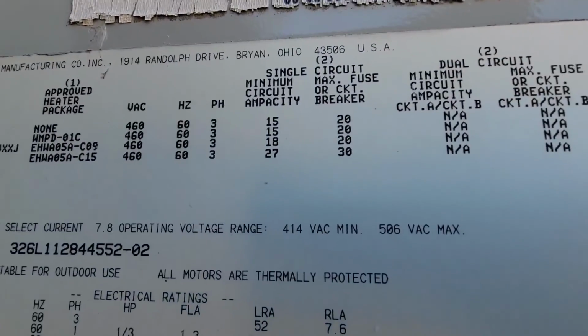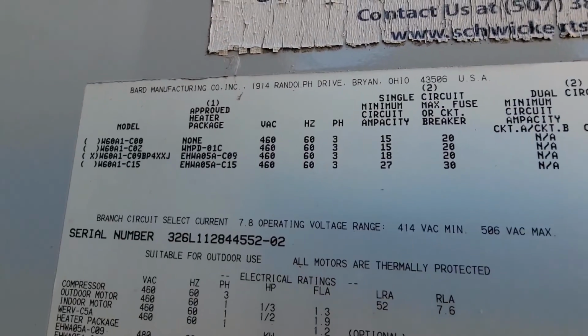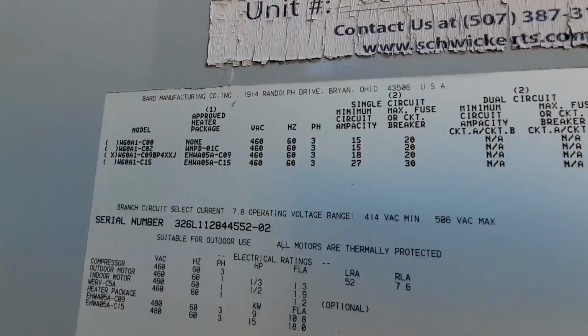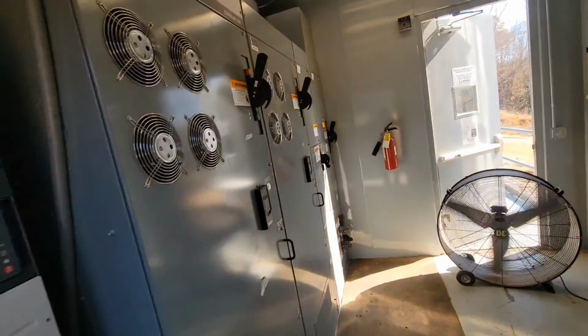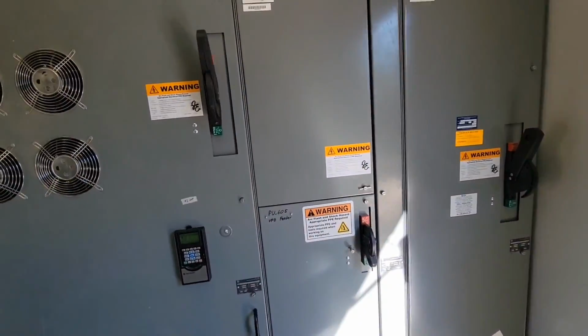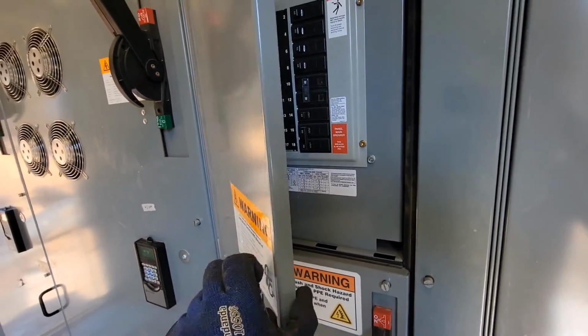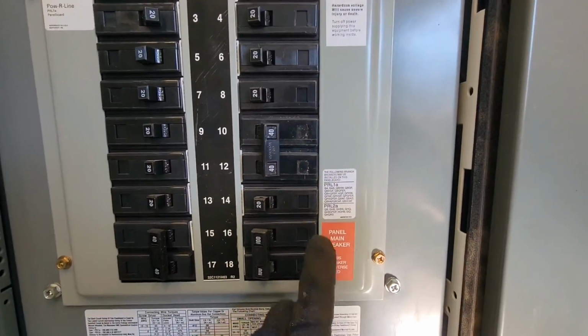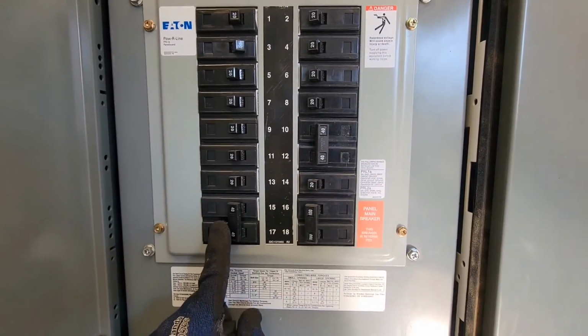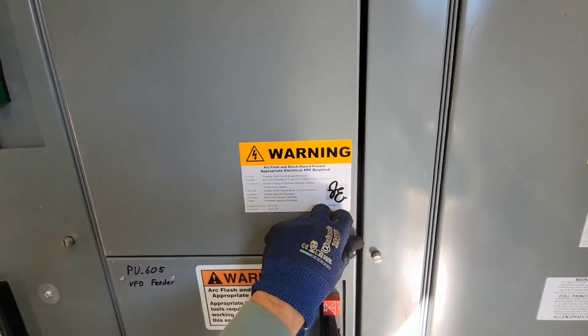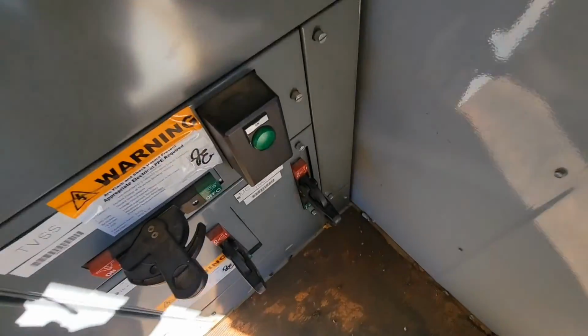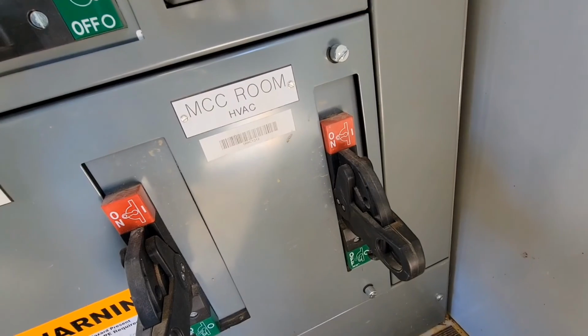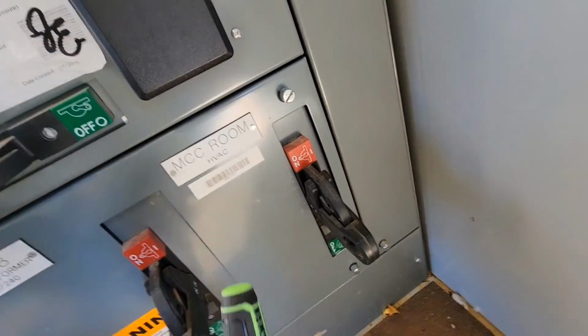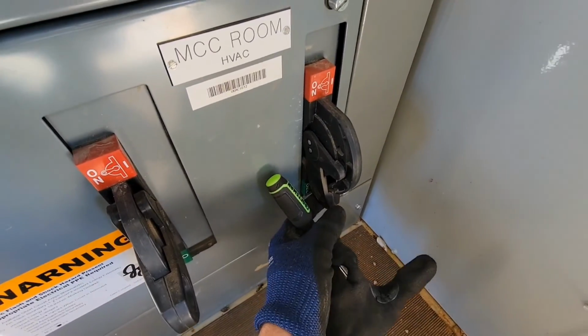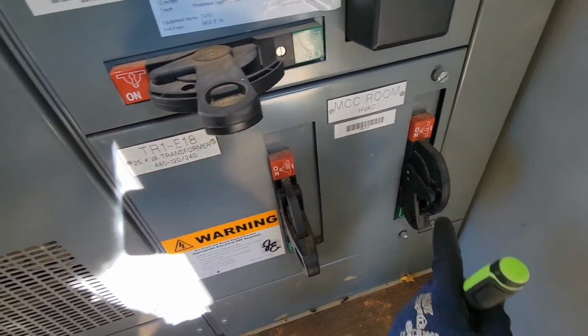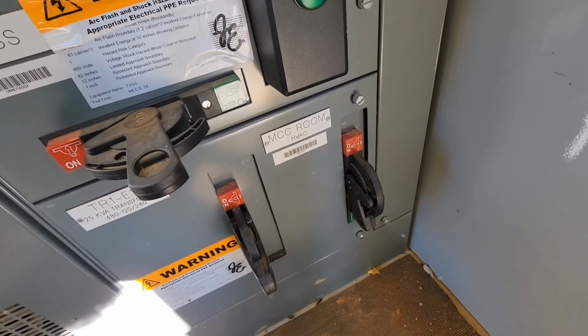Okay, so it says it should be a 30 amp breaker depending on the model, and it's 460 volt. Wow. So where are the breakers? Oh, probably right here. There's a 40 that's off and another 40, but those aren't 3-phase, so this is not it. Let's check around. Down here, HVAC, MCC Room. Okay, so we're going to flip that off. We're going to open up this panel, see if there's fuses.